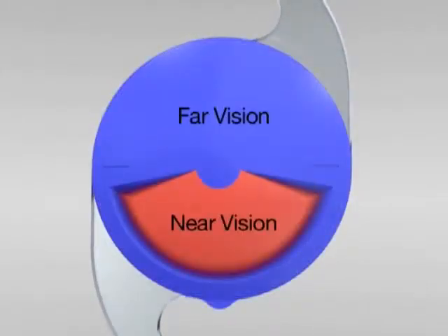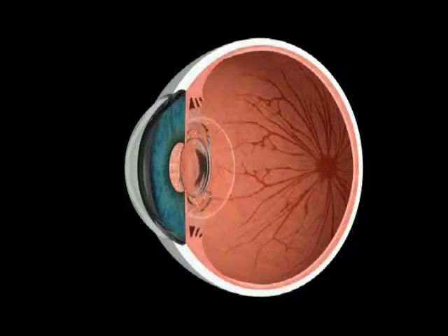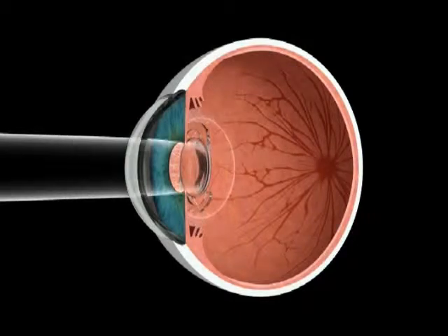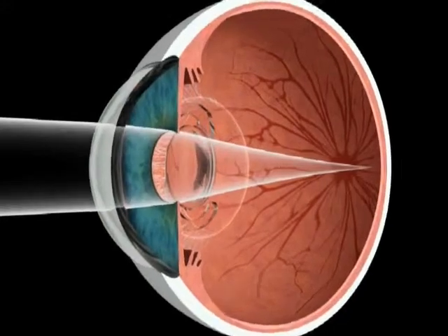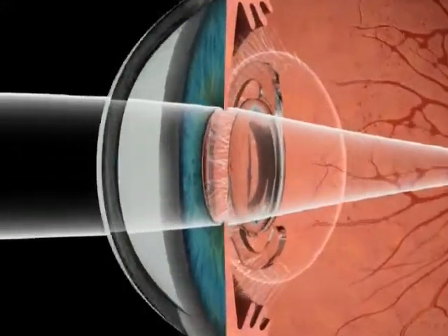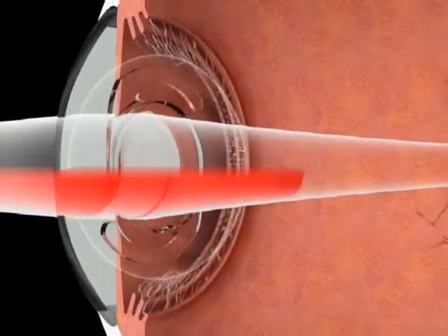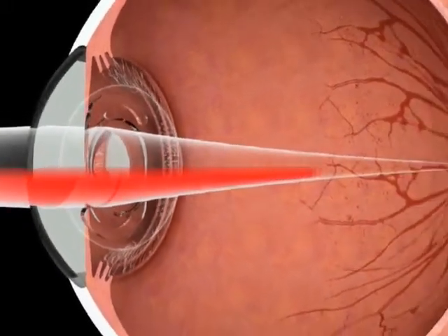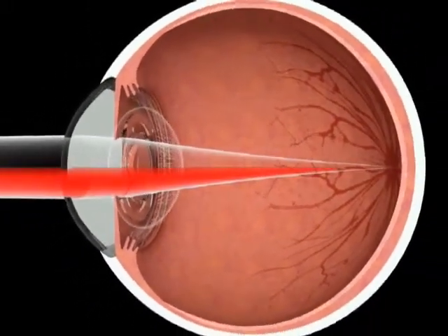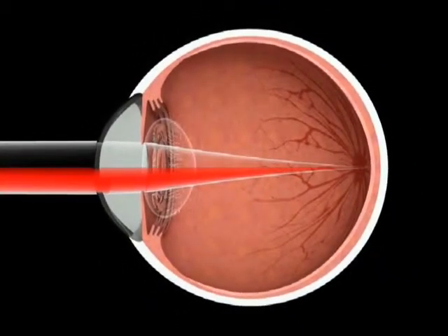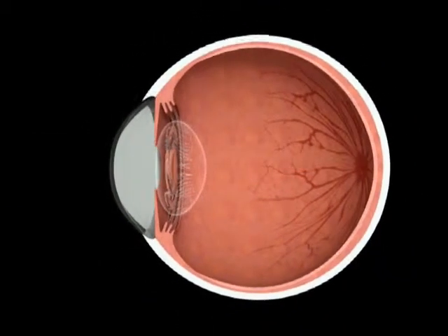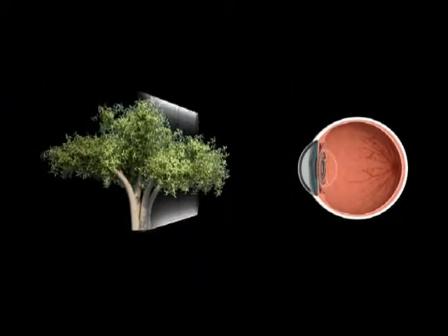The very steep semi-meridional transitions between the reading and distance sectors of this lens minimize the reflections in the direction of the optical axis. When the light hits the transition area in the embedded sector, this will be reflected away from the optical axis. This prevents any superposition of interference diffraction, normally caused by curvature variations on optical surfaces. This will result in a minor loss of light intensity and at the same time a significantly improved contrast sensitivity.